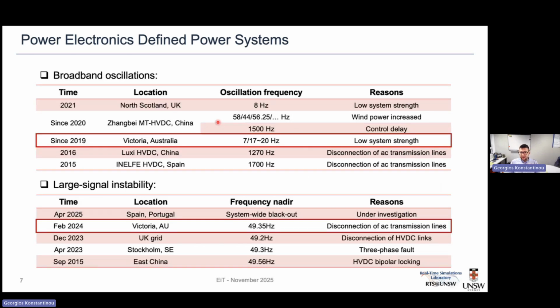This is a problem we are experiencing around the world in different cases. Some examples of low-frequency broadband oscillations have been seen around the world, happening at low frequencies. The example we usually look at here in Australia is in the wider area of the state of Victoria, where we have had, since 2019 continuing all the way to 2023-24 until this issue was finally resolved, low frequency oscillations around 7 to 17 hertz, sometimes up to 20 hertz, continuing for a few hours at the worst cases, happening mostly because of low system strength.